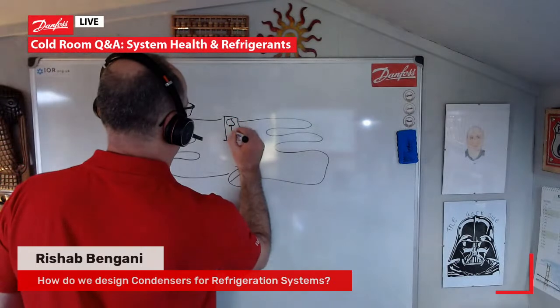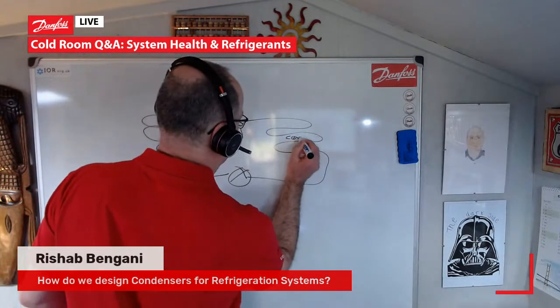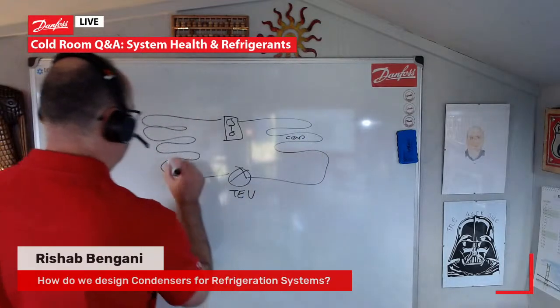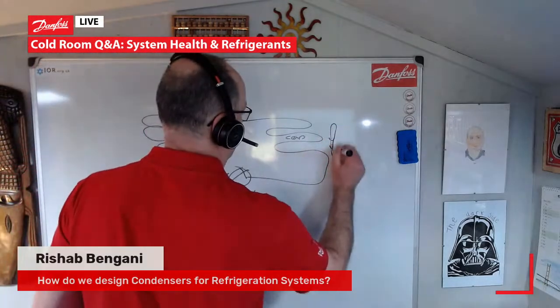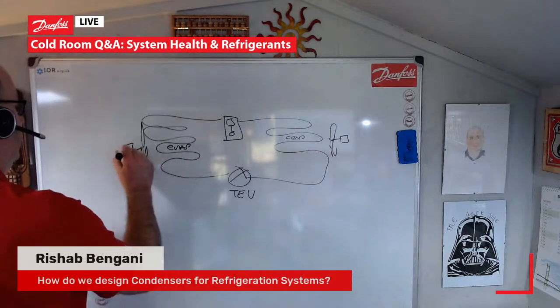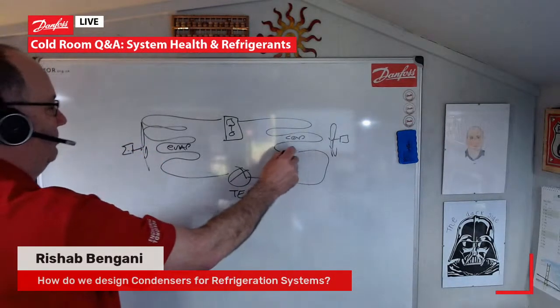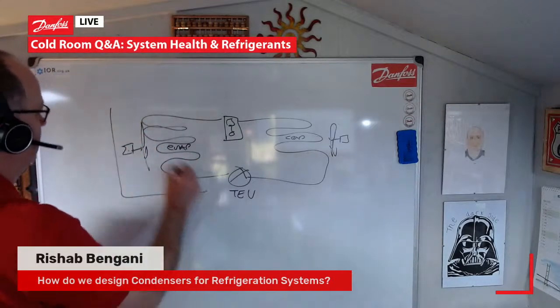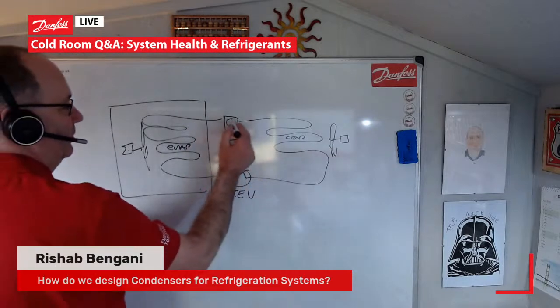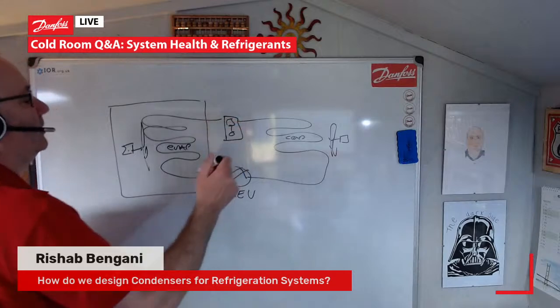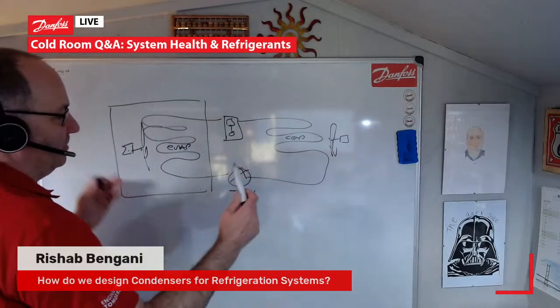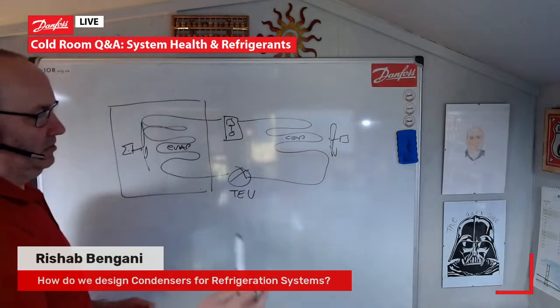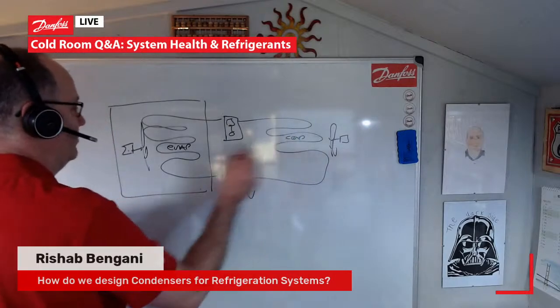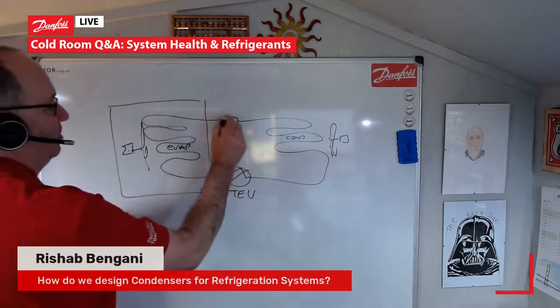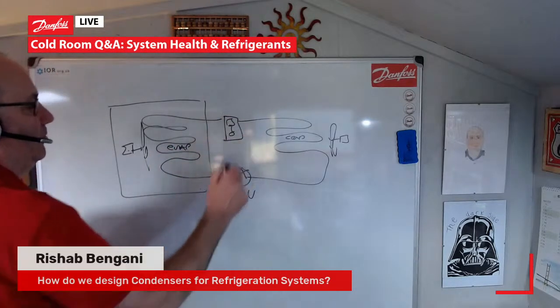So we've got our compressor, that's our condenser, that's our expansion device, that's our evaporator. We've got a fan on that one and a fan on that one. So the condenser basically has to reject the heat that we're removing from our evaporator that's in our cold room, for example, but it's also got to remove the heat of compression from the compressor or compressors, depending on the size of the system. So that's the sort of simplest answer to the design of a system, is the condenser has to remove the heat that we remove from the evaporator, but also the heat of compression that we generate within our compressor as well. So that is a sort of simple answer to a quite technical question.